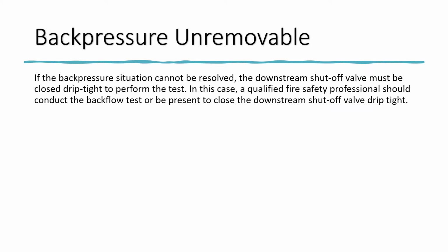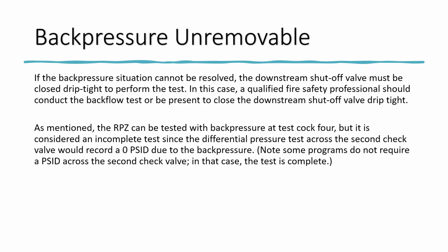If the back pressure situation cannot be resolved, the downstream shutoff valve must be closed drip tight to perform the test. In this case, a qualified fire safety professional should conduct the backflow test, or be present to close the downstream shutoff valve drip tight. As mentioned, the RPZ can be tested with back pressure at test cock 4, but it is considered an incomplete test, since the differential pressure test across the second check valve would record 0 PSID, due to the back pressure.